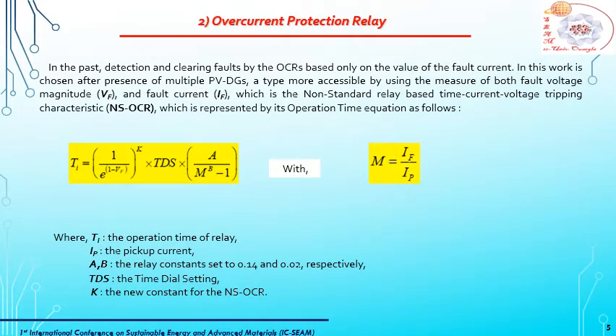In the past, detection and clearing of faults by the overcurrent relay was based only on fault current. In this work, after the presence of multiple PV-DG, a more suitable type is chosen, which uses the measure of both fault voltage and fault current, which is the non-standard relay-based time current voltage tripping characteristic. And it is represented by its operation time equations as follows.